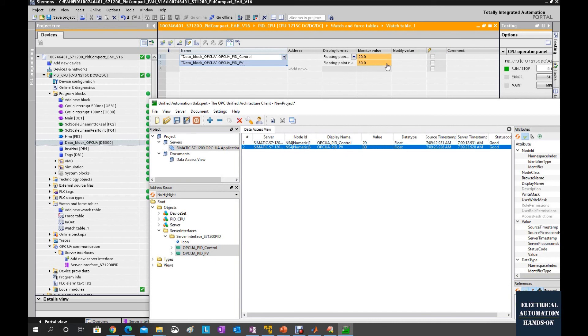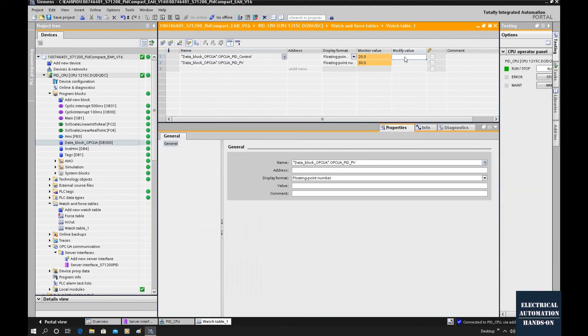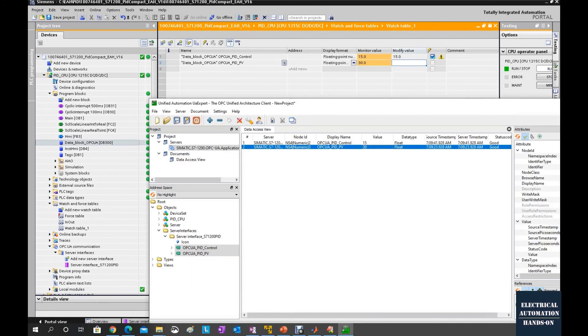We can also write from the PLC side — for example, write a value of 15. That means the OPC UA function is already working successfully inside this controller. Currently we haven't connected these two tags into the PID controller yet.